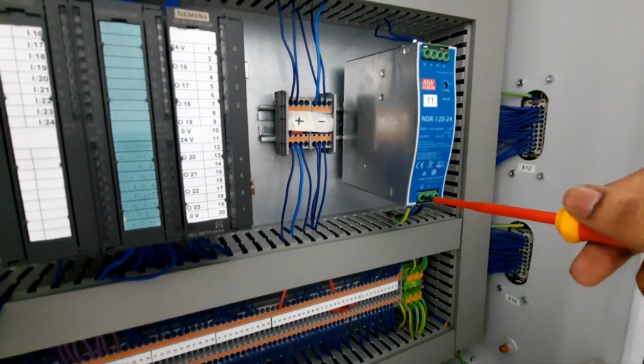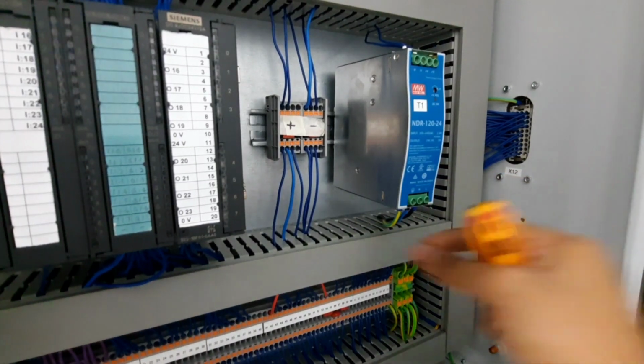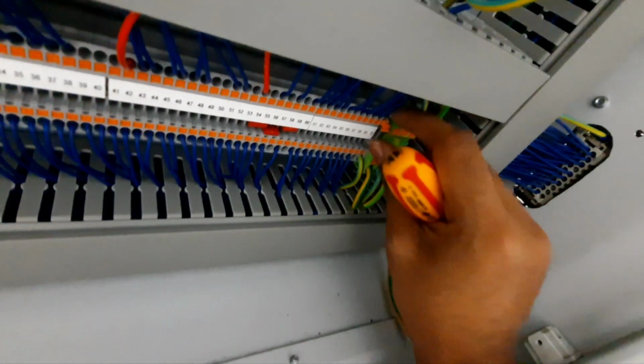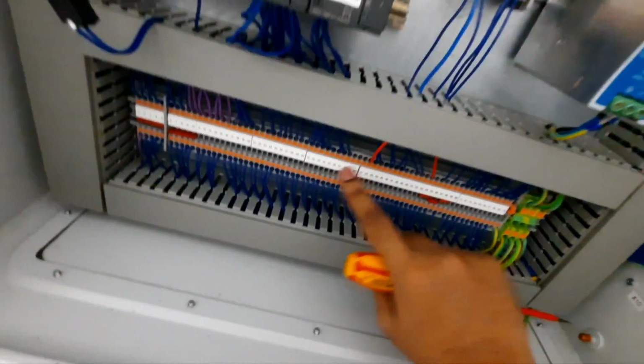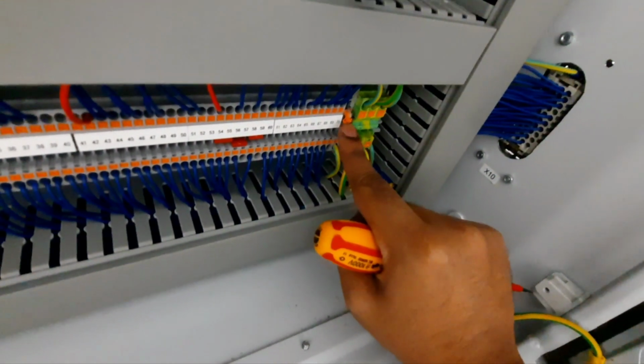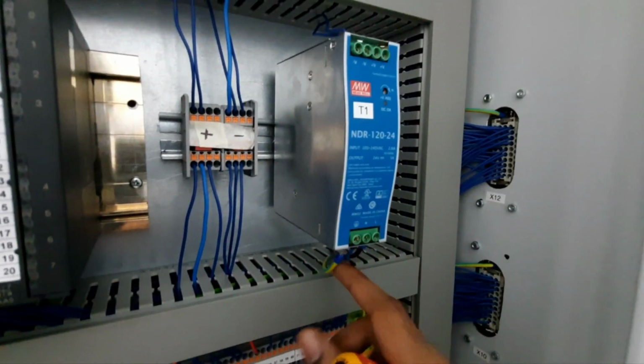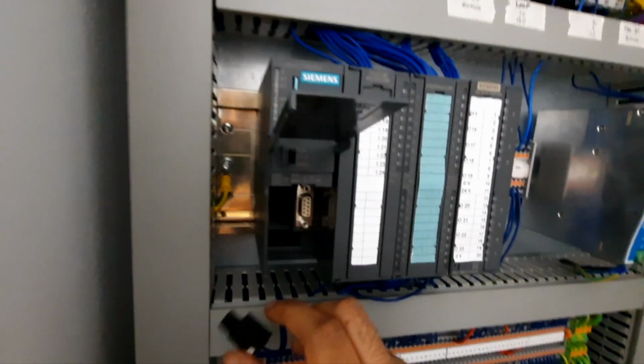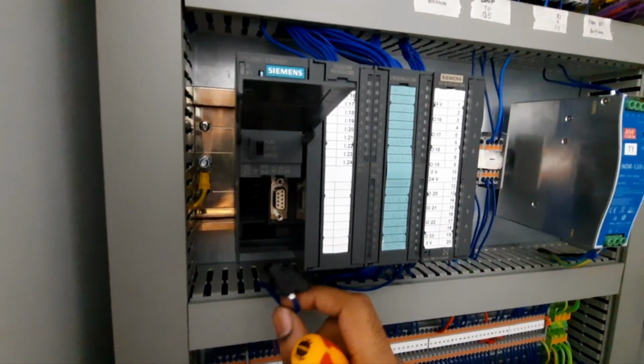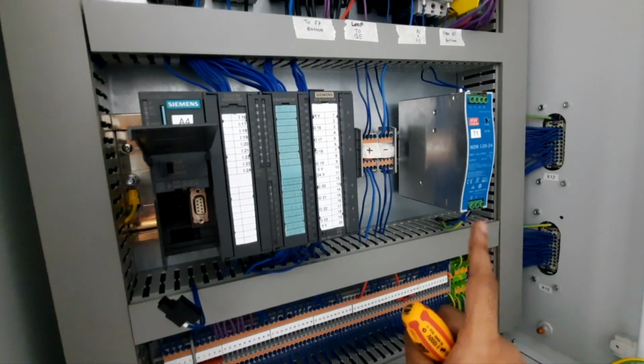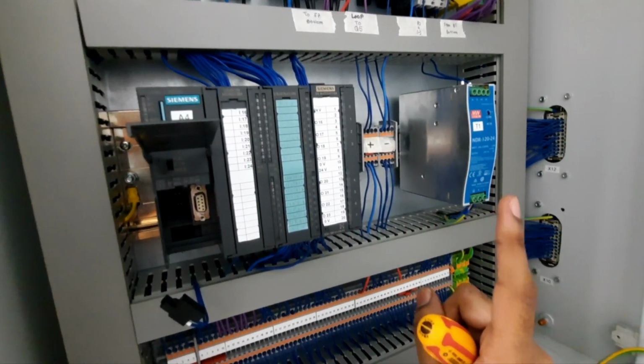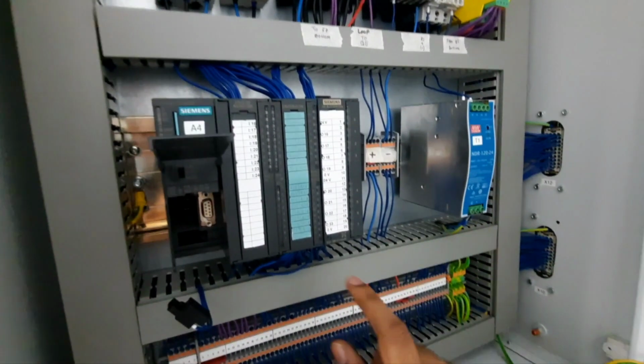You have to take out the PE for the transformer, and then pull this one out too. So three things: the X1 terminal, the PE part, and your PLC power connection. You might see this in your PSCC or Bosch cabinet. All three must be disconnected when you do insulation testing. Insulation means you pump 500 volts and you should get more than 1 mega ohm, for example L1 to E.